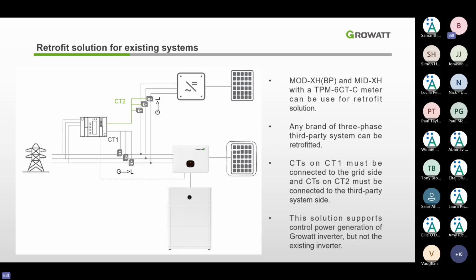Then on our Growatt Shine app, for example, or server, you will be able to see how much generation comes from the first one, and we can use it to charge our battery. But the only thing is we can't really control the first string inverter, so we can't limit it. Export limiting would be a problem for that. But as long as there's no export limitation requirement, then feel free to use the 6CT function. This product is suitable for both MOD and MID XH, and it's called the TPM-6CT-C meter.